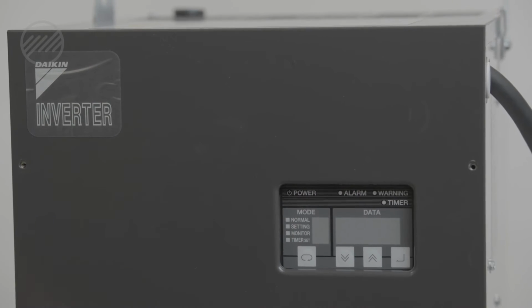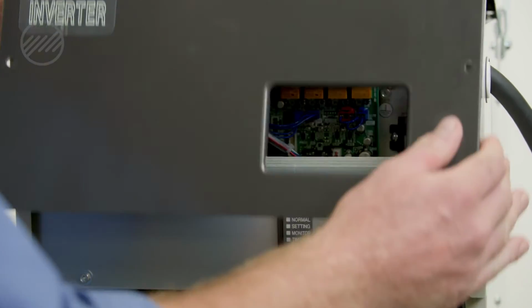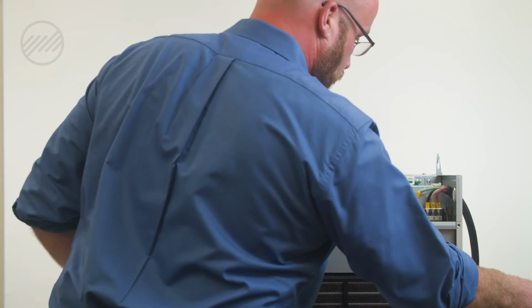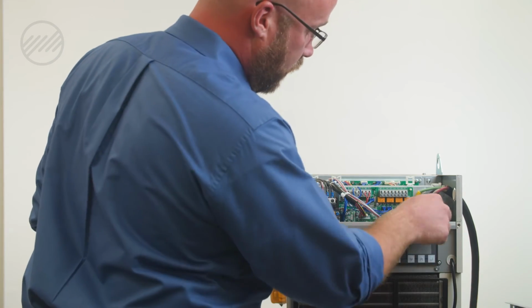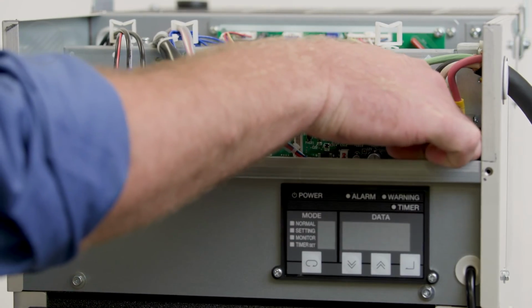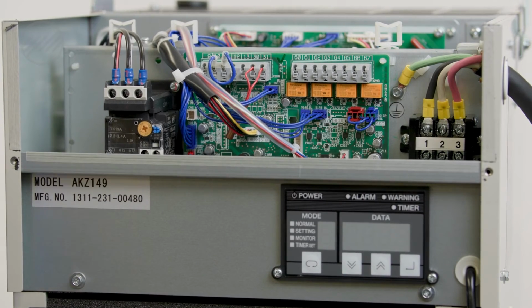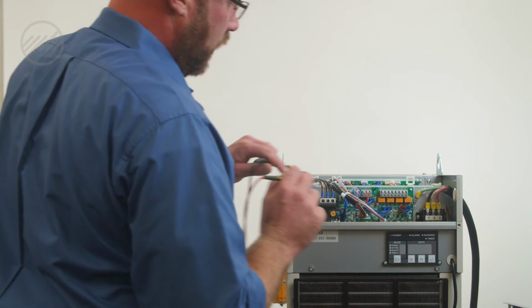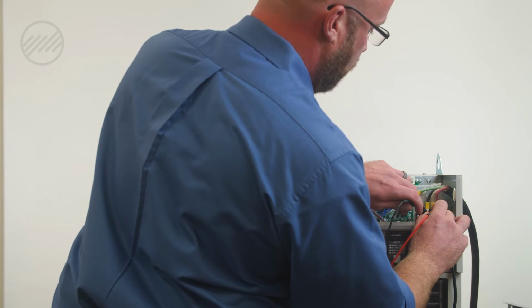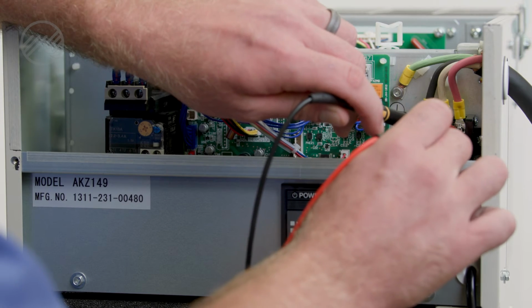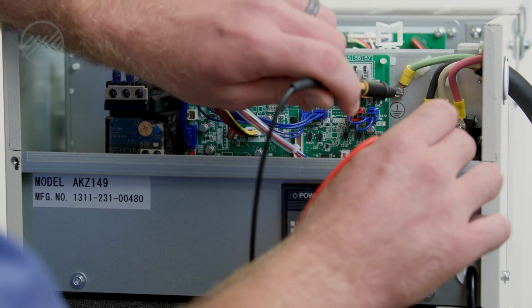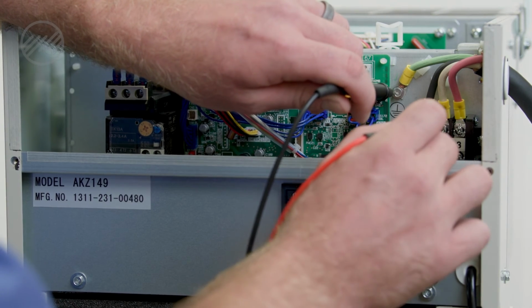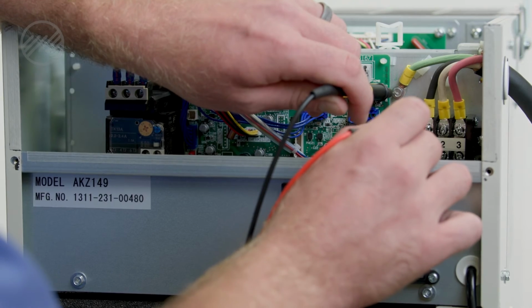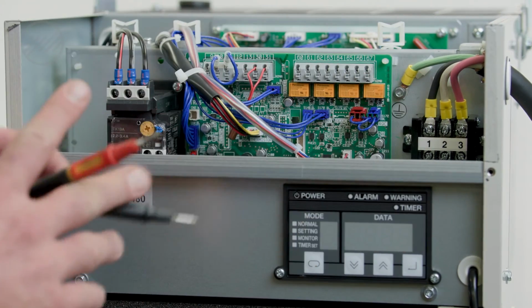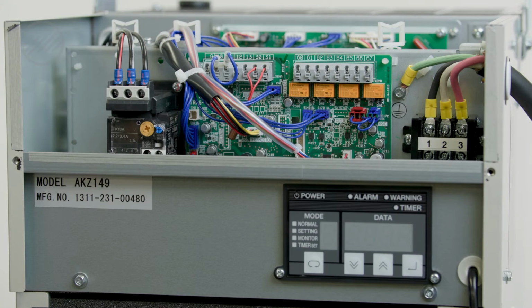When diagnosing a U2 alarm, you'll need to remove the top panel, go to the main voltage incoming, remove the plastic cap, check leg to leg to ensure your voltage is at 200 between legs, and then also check each leg to ground to ensure there is no short in the wiring. If voltage is good and there are no shorts in the unit, it will be your CPU board.